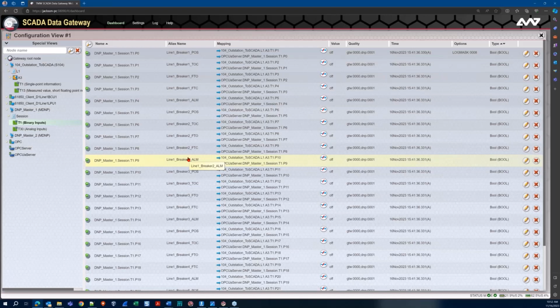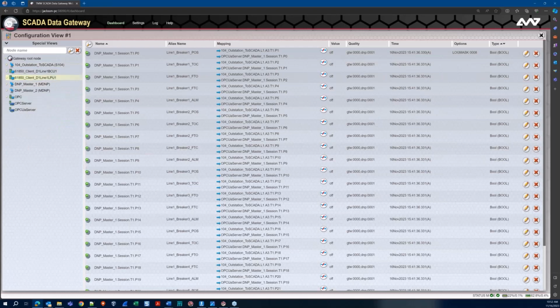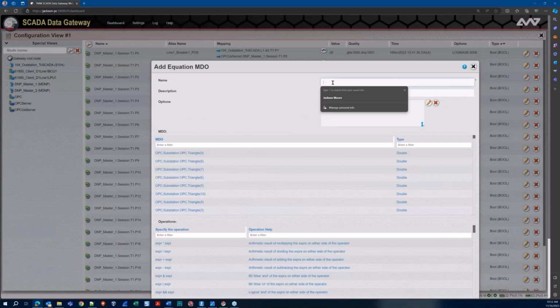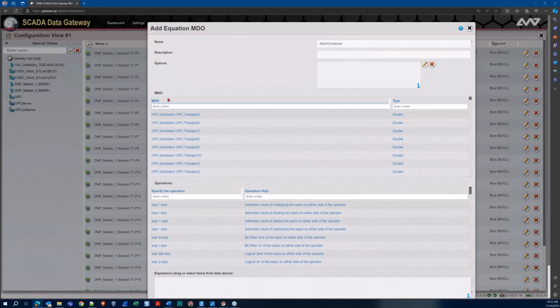That can be done within the gateway, and a lot more, using equations. Equations are a complex point type that let you operate using logic. To create one, start at the gateway root node, right click, and select Add Equation MDO. I'll name this one 'alarm combiner.' Then in the MDO filter, I look for every point available in my gateway, find it, and add it down to the expression builder at the bottom.